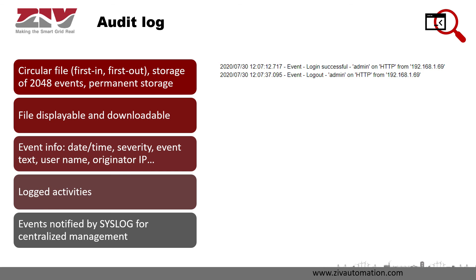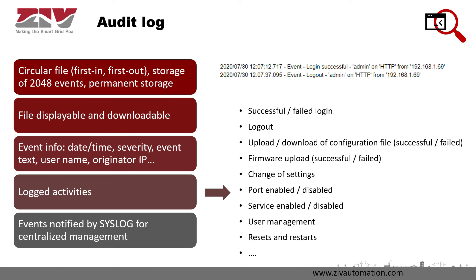Some of the logged activities include: successful and failed login, logout, successful and failed upload and download of configuration files, successful and failed firmware upload, change of settings, port and service enabled or disabled, user management such as creation, deletion or modification of a user or role, certificate management, resets and restarts of the IED, etc. All these events are sent to up to three servers using Syslog, which enables centralized management of all cybersecurity events.